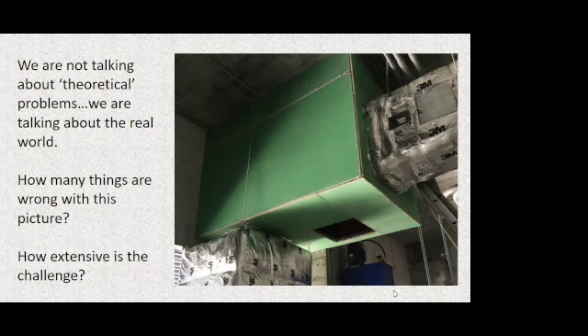Unfortunately, there is nothing fire rated about what we're looking at. We can break it down, but the strap that you see connecting it to the wall, I assure you, other than a duct that's smaller than 16 inches, there is no gripple wire in fire duct land, and there is no strap in fire duct land other than for very, very small ducts. The duct on your right is about 2 feet by 2 feet.